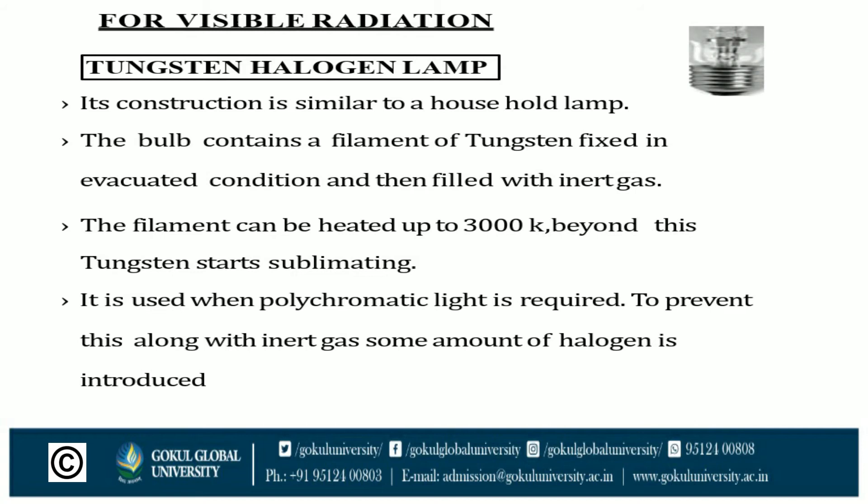For visible wave radiation, various lamps are used. The first is the tungsten halogen lamp. Its construction is similar to a household lamp. The bulb contains a filament of tungsten fixed in an evacuated condition and then filled with an inert gas. The filament can be heated up to 3000 Kelvin, beyond which tungsten starts sublimating. It is used when polychromatic light is required. To prevent sublimation, along with the inert gas, some amount of halogen is introduced.